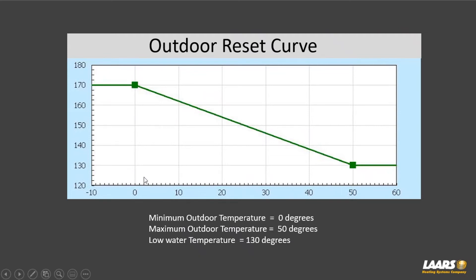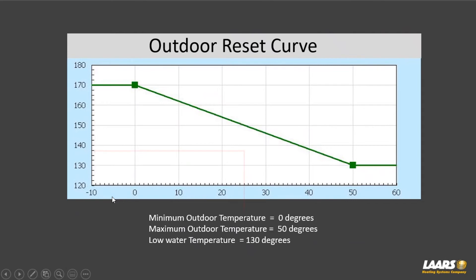That zero-degree minimum is your design temperature for your region. Boston, Massachusetts might be 10 degrees above zero, making the minimum outdoor temperature 10. In Minneapolis it might be minus 5. Your maximum outdoor temperature in this example is 50 degrees with a low water temperature — meaning at 50 degrees we'd only deliver 130. On the design day at zero degrees, we'd deliver 170. At 25 degrees outdoor temperature, we'd deliver 150 to the heating system.